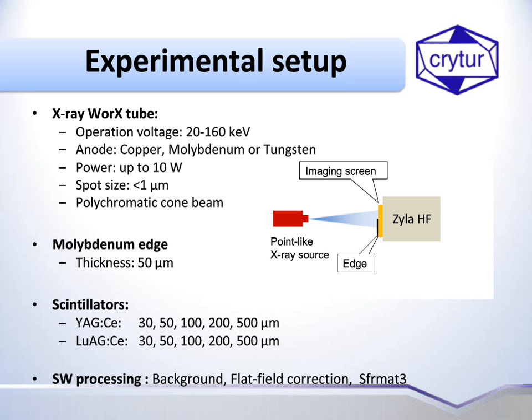These were freestanding scintillators, but we also had a chance to test a scintillator which is glued to fiber optics, which will be coupled to another fiber optic input of the Zyla. After we measured these images, we need to do some processing, which would be background and flat field correction, and then the processing in MATLAB to get the MTF of the system.